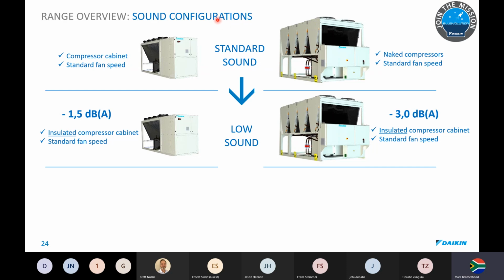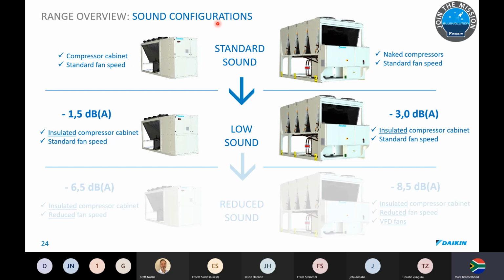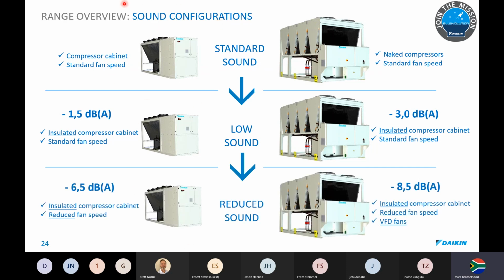Very importantly, a lot of sites are very pedantic about sound. So in the V block range, we offer a standard option sound. We offer then low sound as well as reduced sound, minus 1.5 dBs. These are normally taken at a 1 meter distance from the chiller. So what do we do? We insulate the compressor cabinet. So if you open this cabinet, there's foam padding being put in here. And to drop it even more, we insulate the cabinet and we reduce the fan speed for head pressure control.